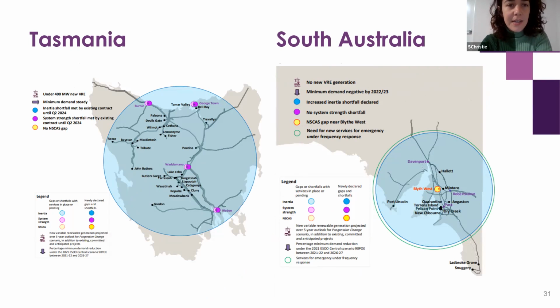On the left here you can see Tasmania, separated from the mainland and down to the south. This region happily has hydro available, so although they've had system strength shortfalls and inertia shortfalls declared for quite some time, they've been able to address them through agreements with existing synchronous generators that are hydro powered, some of which also have the capability to operate in synchronous condenser mode.